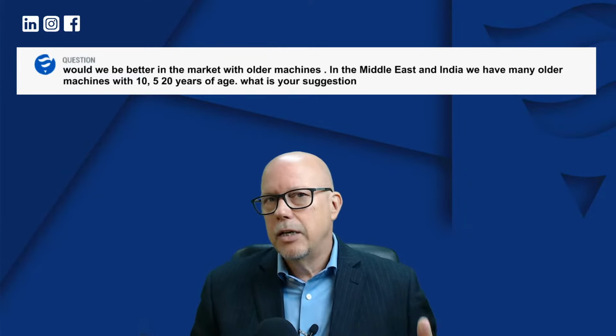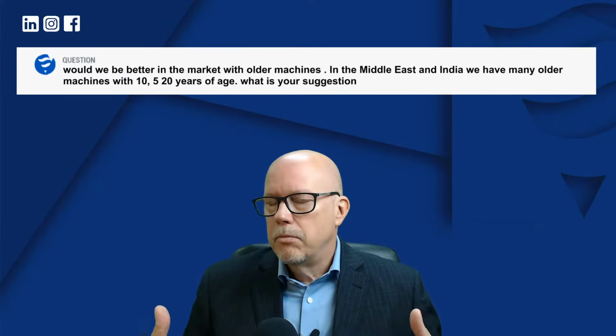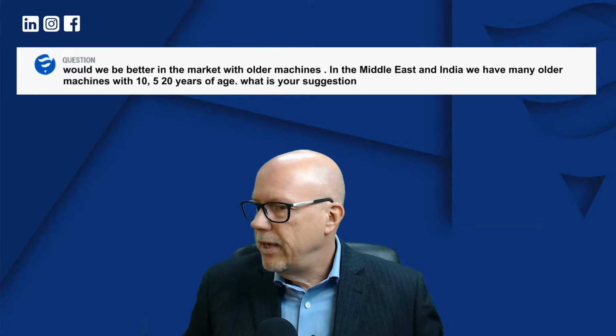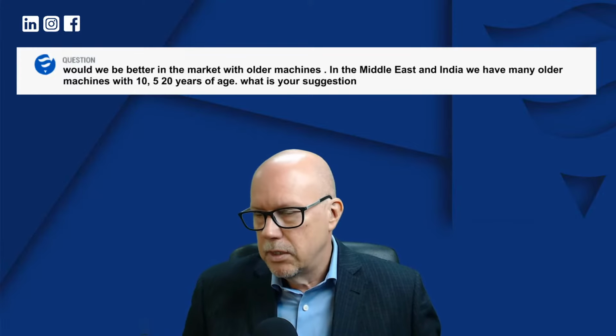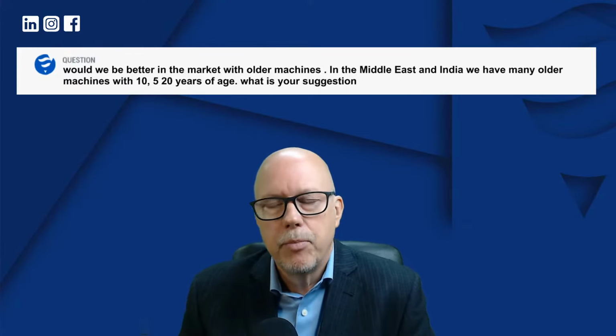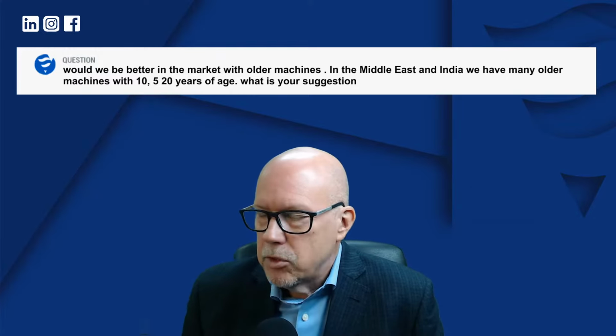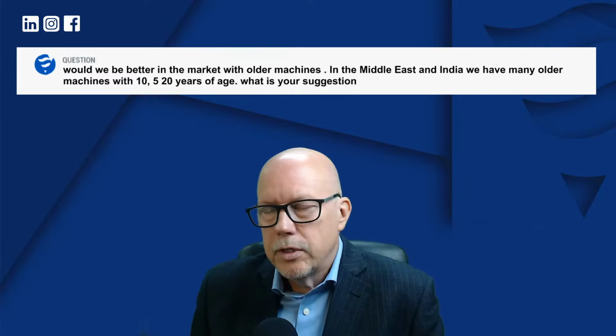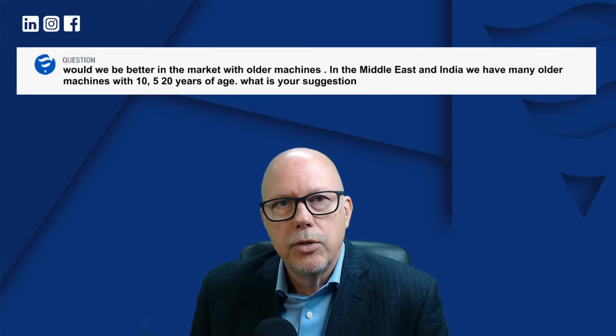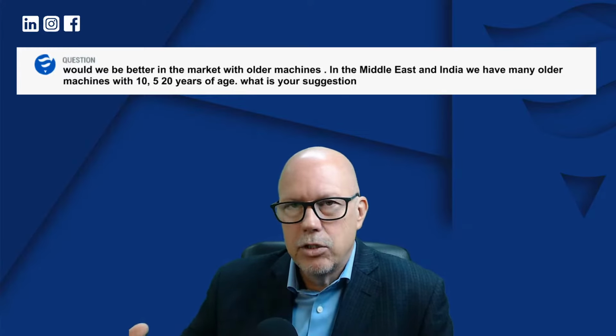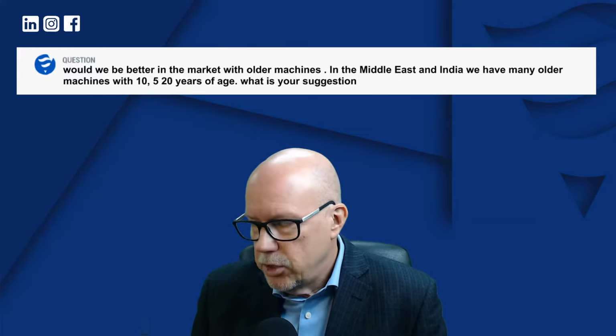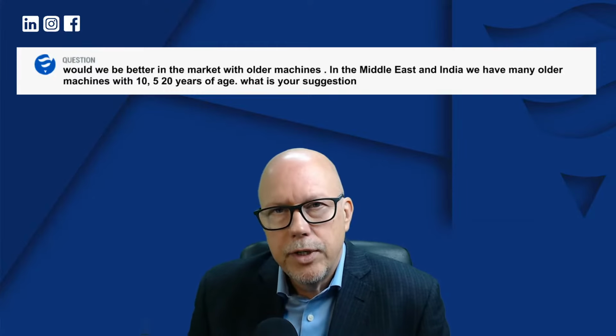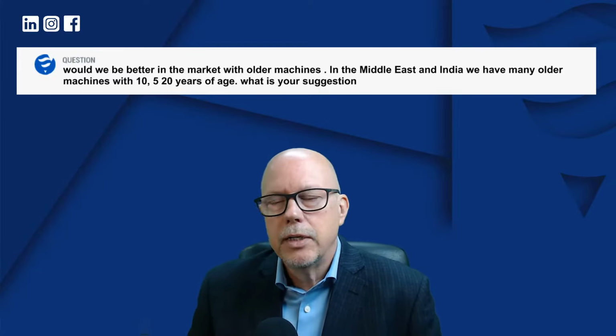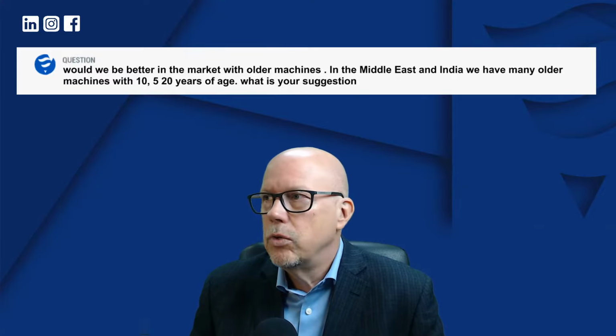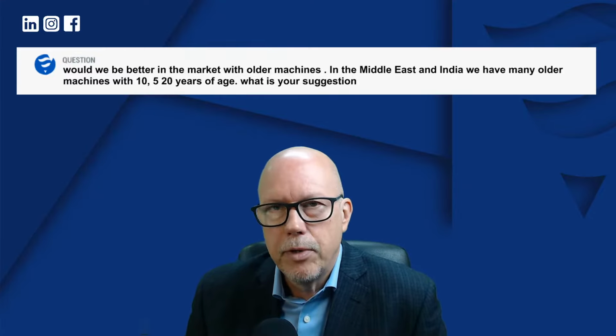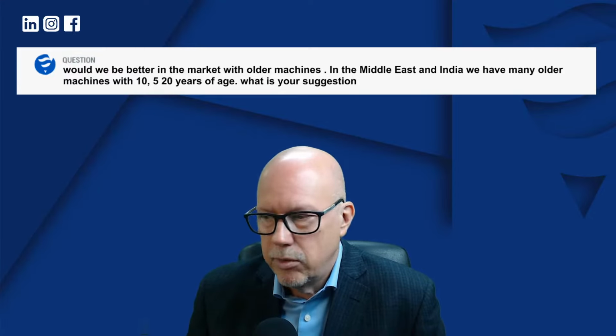Now, if you start cycling these units, most experts expect premature failures because of this change in operating condition. So for new units, I would put in a monitoring system to make sure that the units that are delivered, which are at the edge of technology, meet the specifications. If I had 10 to 20-year-old units, I would put in monitoring to see if these new constraints or operating conditions are causing any damage to my unit.